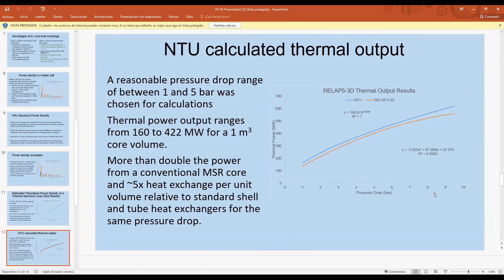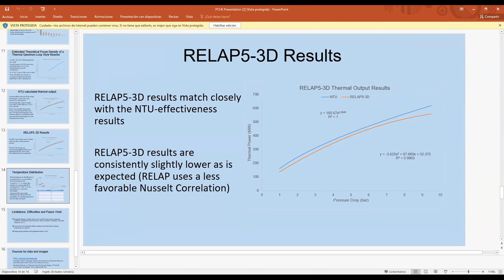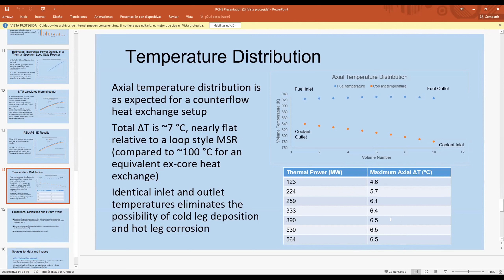And these are all for fairly reasonable pressure drops. We're only getting maybe 1 to, on the higher end, 9.5 bars. That's the highest pressure drop that you're seeing here. And we find that these results are matching fairly closely, both for the hand calculations done using the NTU method, as well as the simulations done in RELAP5-3D. So this is the temperature distribution that we were discussing earlier. We'll see that our axial distribution for a counterflow setup has a maximum delta T on the lower end of 4.6 degrees C. That's for a slower flow rate and lower thermal power. And then on the higher end, we're seeing as much as 6.5 degrees C. So that's a very low temperature distribution.